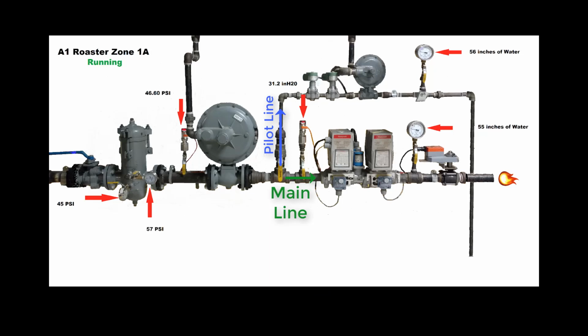Once the pilot is lit, the FSR opens the main and blocking valves. The pilot is now used as an ignition source for the main burner, and a much bigger fire is created. A control valve is used in line with the main line in order to control the intensity of the main burner, and by doing so controls the amount of heat in the roaster and dryer.